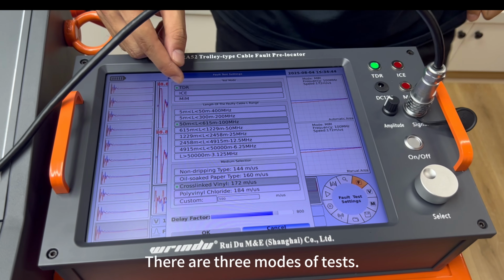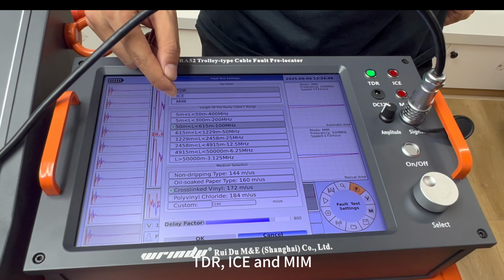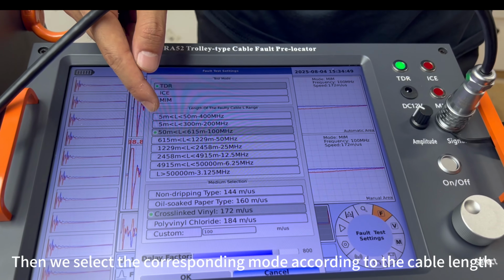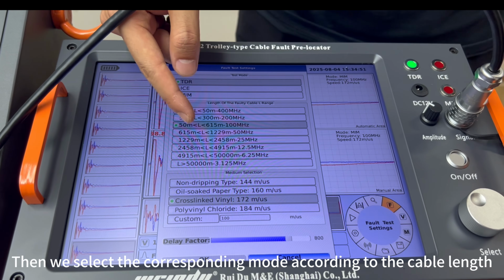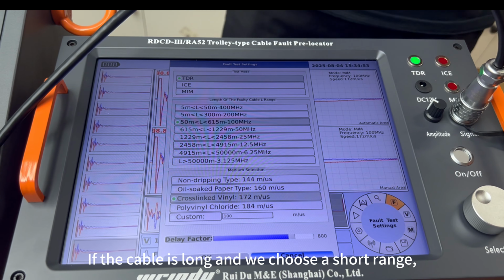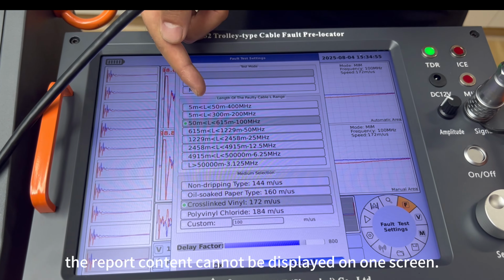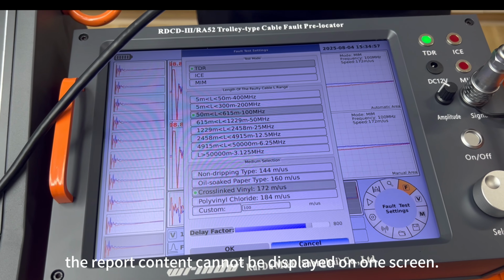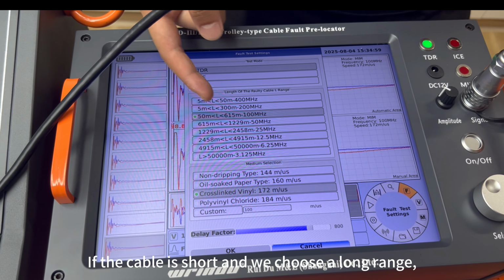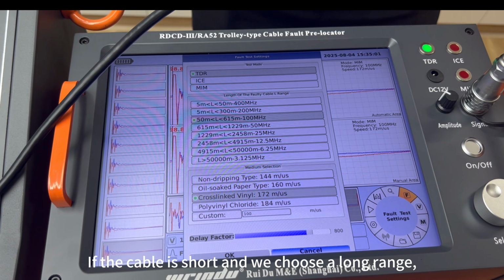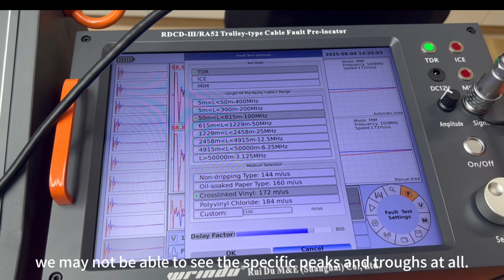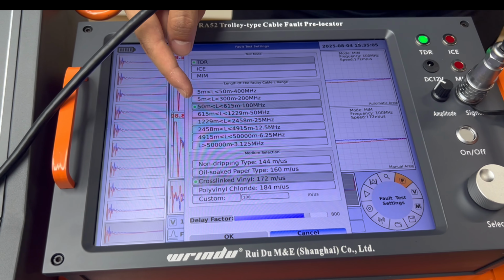There are 3 modes of tests: TDR, ICE, and MIM. Then we select the corresponding mode according to the cable length. If the cable is long and we choose a short range, the report content cannot be displayed on one screen. If the cable is short and we choose a long range, we may not be able to see the specific peaks and troughs at all.